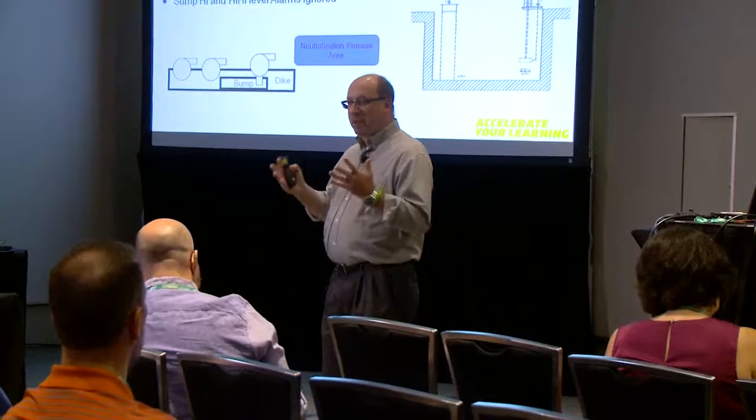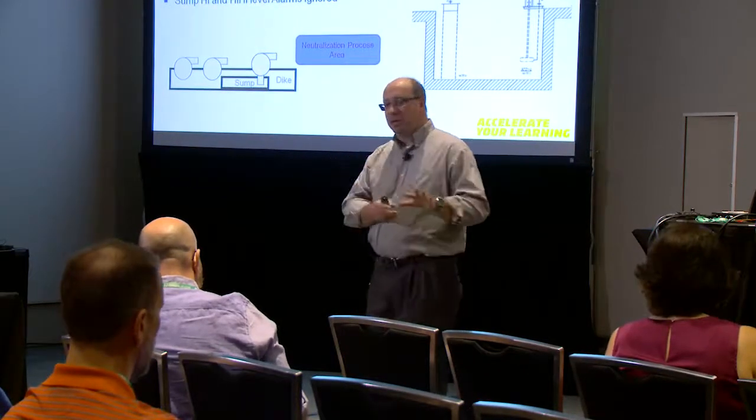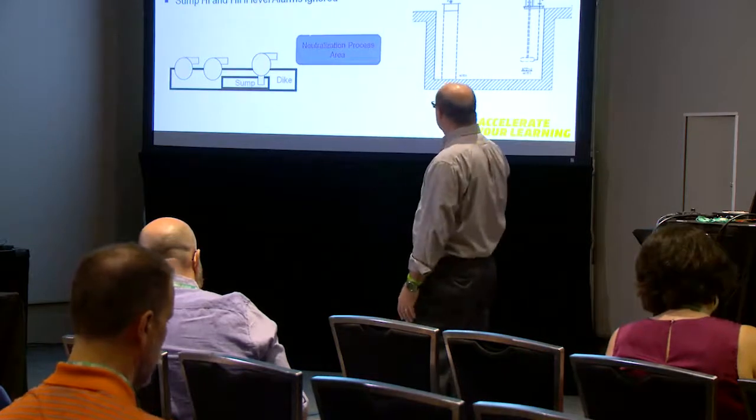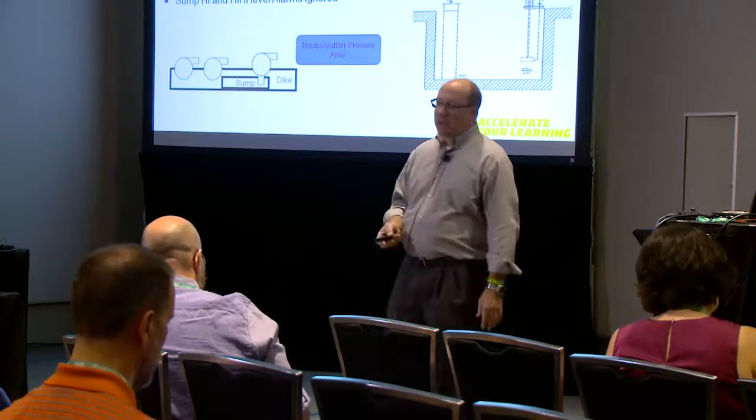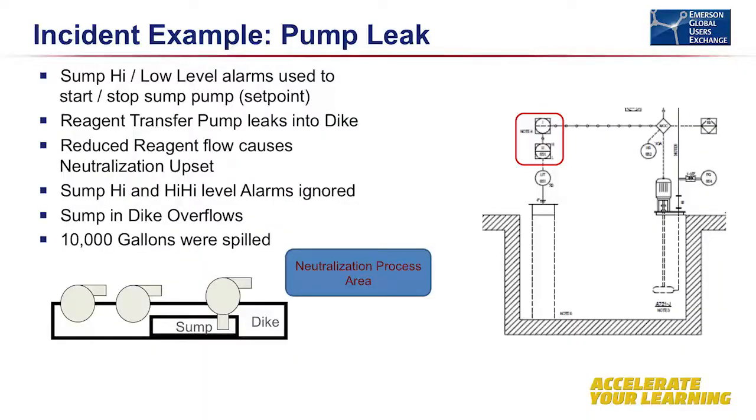So with that as the background from a human factors point of view, they felt that they could ignore that, and they focused only on the neutralization area as where the problem might actually be, which was incorrect. So they ignored those alarms because they were used to doing it. That's what they'd always done. And unfortunately, things got worse.